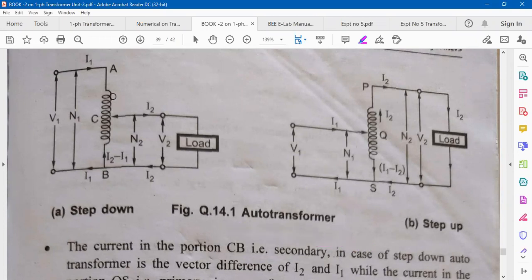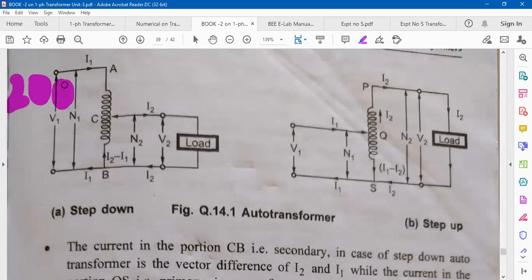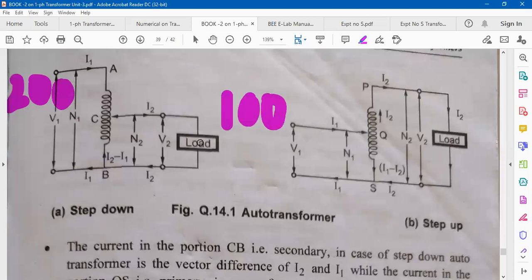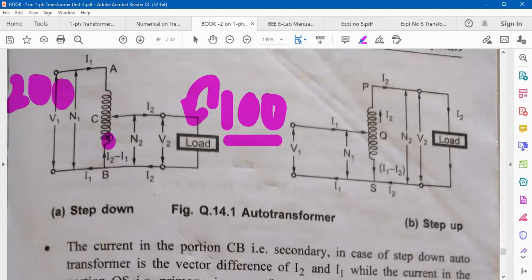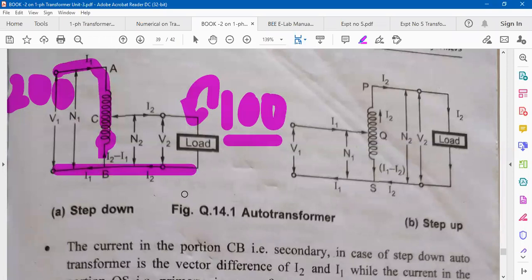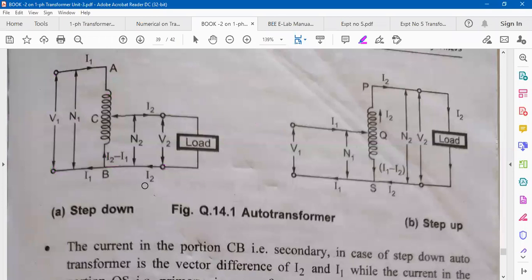The disadvantage of the autotransformer is that primary and secondary turns are electrically common. For example, in a step-down configuration with 200V primary and 100V secondary, if an open circuit occurs in the winding, the full 200V would appear across the load that is designed for only 100V. This is a safety hazard. As long as no open circuit occurs, it is safe to use. Windings must remain continuous between primary and secondary terminals.